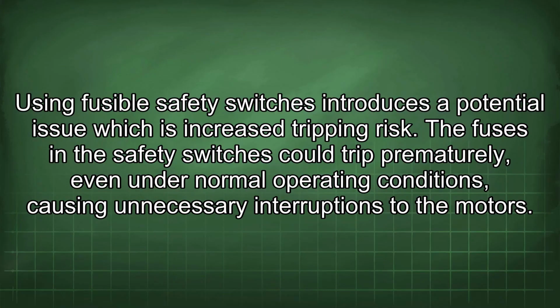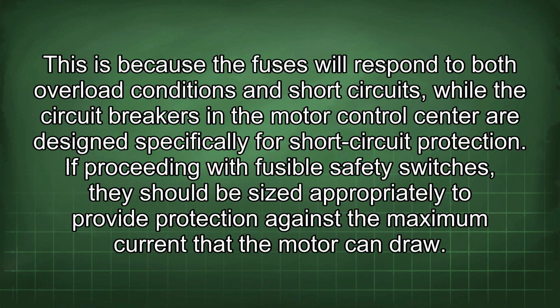Using fusible safety switches introduces a potential issue, which is increased tripping risk. The fuses in the safety switches could trip prematurely, even under normal operating conditions, causing unnecessary interruptions to the motors. This is because the fuses will respond to both overload conditions and short circuits, while the circuit breakers in the motor control center are designed specifically for short circuit protection.